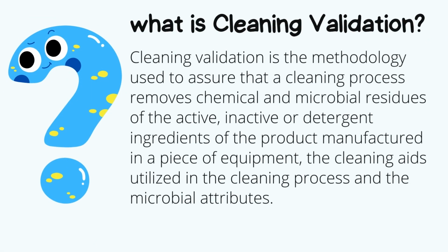Today's topic is cleaning validation. What is cleaning validation? Cleaning validation is the methodology used to assure that a cleaning process removes chemical and microbial residues of the active, inactive, or detergent ingredients of the product manufactured in a piece of equipment, the cleaning aids utilized in the cleaning process, and the microbial attributes.